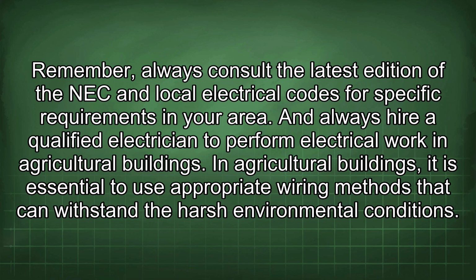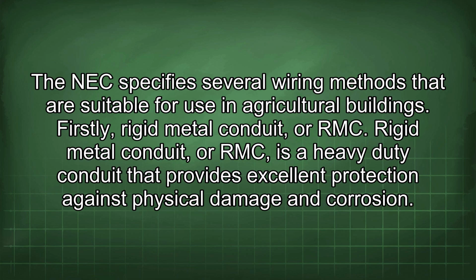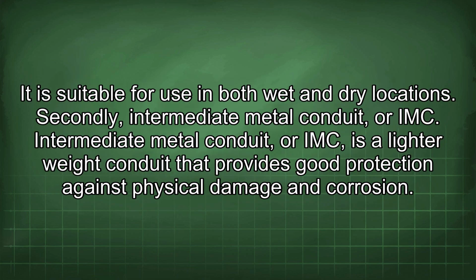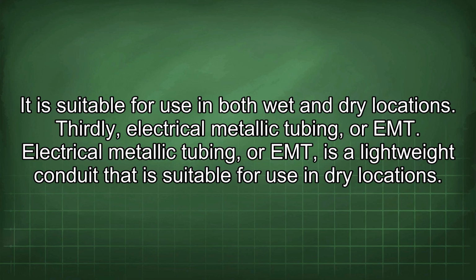In agricultural buildings, it is essential to use appropriate wiring methods that can withstand the harsh environmental conditions. The NEC specifies several wiring methods that are suitable for use in agricultural buildings. Firstly, rigid metal conduit, or RMC. Rigid metal conduit, or RMC, is a heavy-duty conduit that provides excellent protection against physical damage and corrosion. It is suitable for use in both wet and dry locations. Secondly, intermediate metal conduit, or IMC. Intermediate metal conduit, or IMC, is a lighter weight conduit that provides good protection against physical damage and corrosion. It is suitable for use in both wet and dry locations.